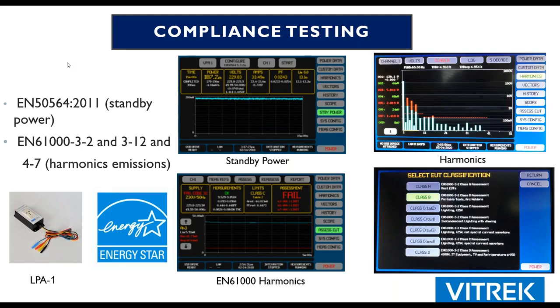We have that for EN 50564, which is a spec for standby power. A lot of measurements are done on electronic devices to make sure that they're Energy Star compliant. Standby tests are when you've got a unit that's not powered up, but it's still drawing some power. The standby power test can be run on a Vitrek power analyzer and get you your test results. Log your data however you want to do it. You'll notice in the lower left-hand side of my screen, I've got a device that Vitrek makes called our LPA-1. That basically eases the connection of a device that plugs into a standard wall outlet.